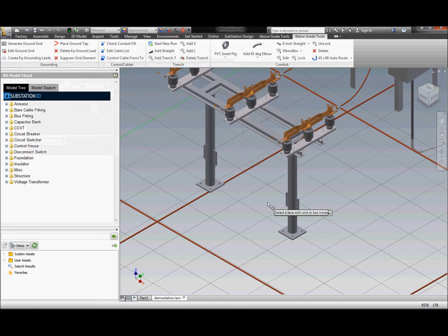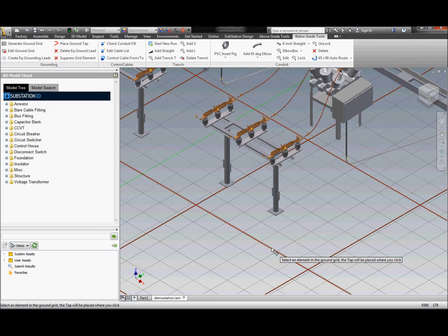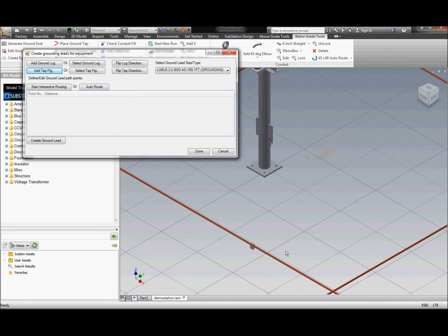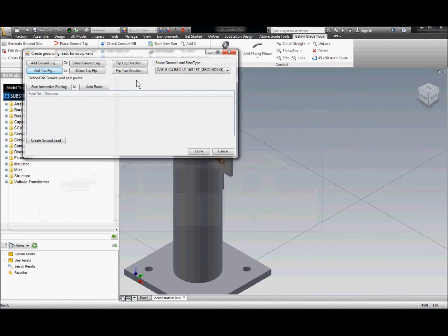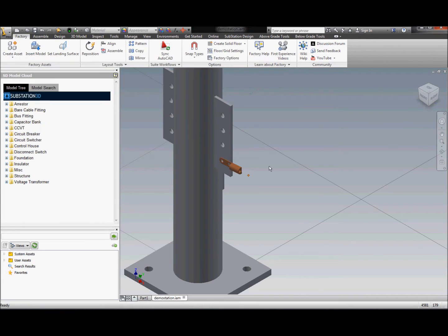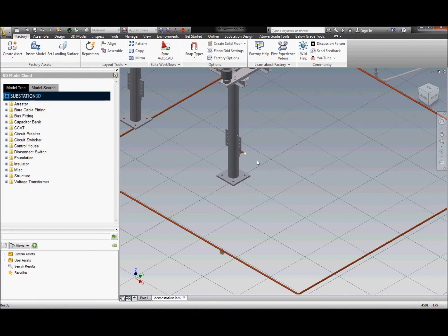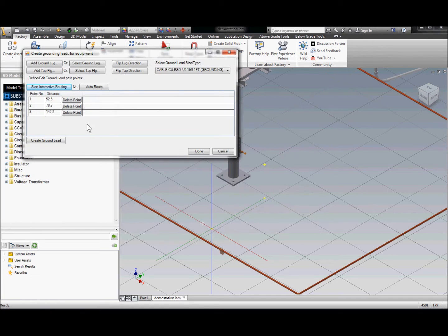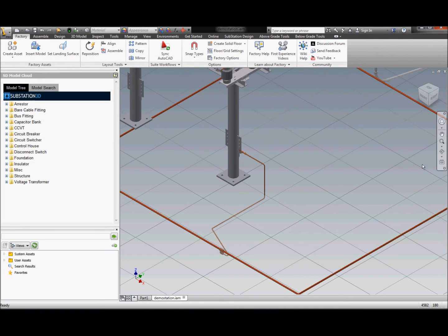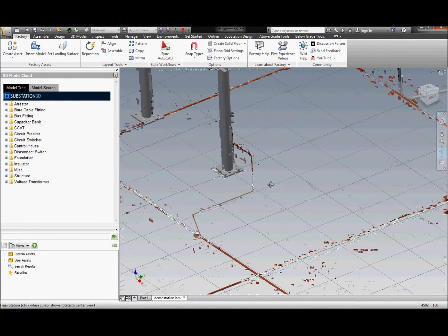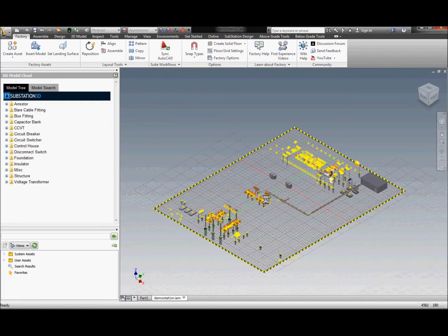We're going to put a tap flange on any piece of rod — just selecting along the rod at any location we'd like — and we can drag that tap lug along the rod as well. Once those two components are in place, we just need to run the lead directly from the lug. In this case the lug is turned the opposite way, so we're going to pick 'flip lug direction' — it's going to turn it around so it's facing away from the equipment. There are small adjustments needed on each piece of equipment depending on orientation within the model. Now let's start a run — the ground lead shows three axes in different colors and automatically generates that ground lead as a true part file in the bill of material. We can gather all the real calculated lengths into a bill of material, as well as the lugs and taps — every time one of these is added, it's a true bill-of-material quantity being added to the overall model.